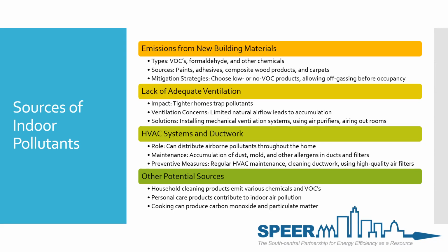So contributing to that is airborne pollutants could get passed around through the house by being distributed through the HVAC system. It's the accumulation of dust and mold and other allergens inside ducts and filters. If you haven't seen what the inside of an old duct system looks like, a lot of times there's a lot of dust accumulation, but on that dust are dust mites, and if there's condensation buildup or high humidity, it can actually condensate inside those ducts and build up mold as well. So there can be a lot of things that are adding to allergens inside the duct system.